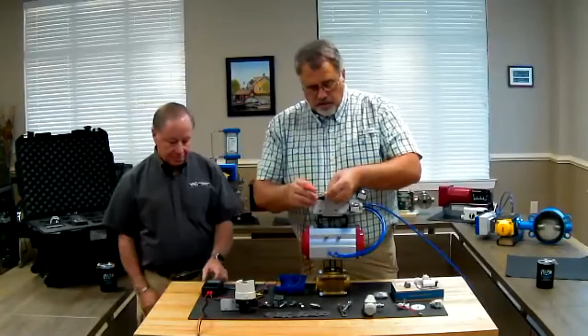I'm going to take my loop calibrator, which is a low-cost unit that we offer for sale. Randy will talk a little bit more about that later. But it's unique in that it will both drive the positioner and read feedback. Turn it on here. Put signal on the positioner. And I've got a 4 milliamp signal on the positioner, and I'm going to do a real quick calibration here.